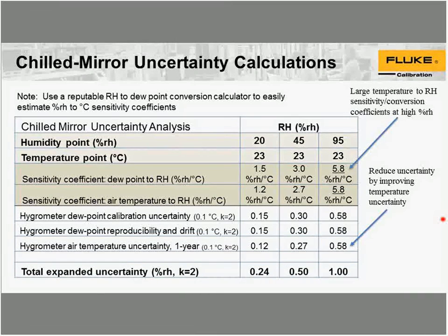How do you calculate the uncertainty budget of relative humidity? That's a good question. That's one of the directions we're contemplating going with our webinar series. Maybe our next webinar will be talking about uncertainty calculation. The trickiest part is we'll convert temperature to %RH, and we use some typical sensitivity values that are used for those conversions. But we're planning on moving forward with this, and one of those materials will most likely have uncertainty analysis in it.